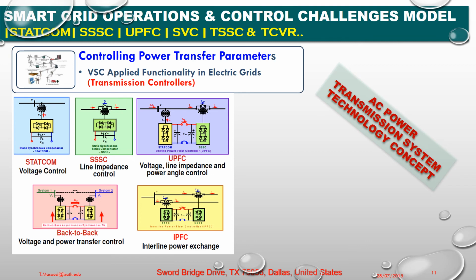Okay, voltage source converter based technology, in which the DC voltage always has one polarity, and the power reversal takes place through reversal of the DC current polarity. So on VSC applied functionality, what we can deliver here: first, the STATCOM, we can control the voltage here. Second, SSSC, static synchronous series compensator, to adjust and control the line impedance. Third, the unified power flow controller, UPFC, controlling voltage, line impedance, and power angle. Number 4, back-to-back STATCOM, voltage and power transfer control here. And number 5, interline power flow controller, IPFC, used for interline power exchange.